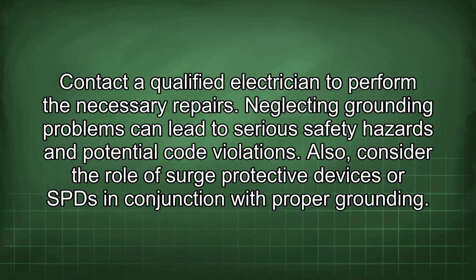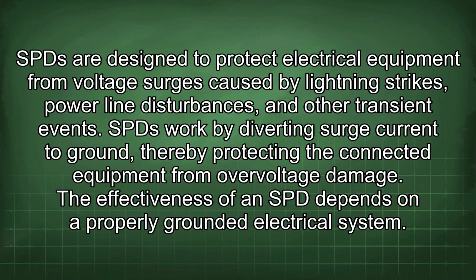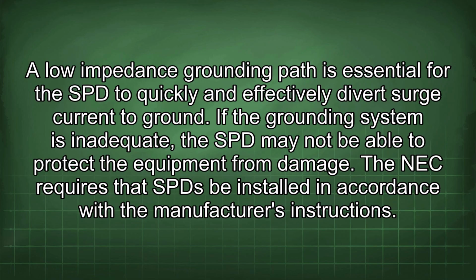Also, consider the role of surge protective devices or SPD in conjunction with proper grounding. SPD are designed to protect electrical equipment from voltage surges caused by lightning strikes, power line disturbances, and other transient events. SPD work by diverting surge current to ground, thereby protecting the connected equipment from overvoltage damage. The effectiveness of an SPD depends on a properly grounded electrical system. A low impedance grounding path is essential for the SPD to quickly and effectively divert surge current to ground. If the grounding system is inadequate, the SPD may not be able to protect the equipment from damage.